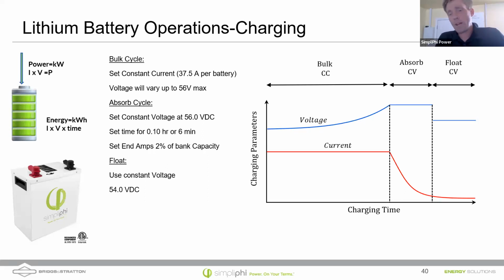Right? But to apply that same current when that battery gets more and more charged, I have to apply greater and greater voltage on the charging equipment. And you'll see that voltage start to rise as those batteries are charging up. We set the end of the charge cycle at what's known as the bulk voltage, and that's 56 volts max. So once the charging equipment hits 56 volts, we are done with the constant current bulk portion of the charge cycle.